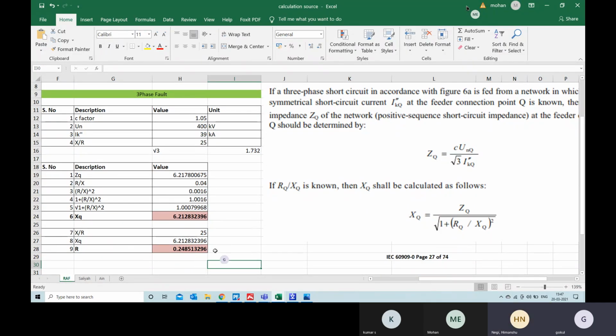As long as you have those values for three phase - if you have the X by R ratio and the fault current, then it's just a matter of minutes to do it. So right now we know the three-phase fault current, or the positive sequence current.